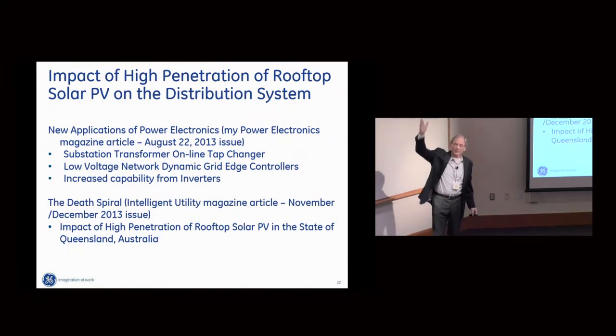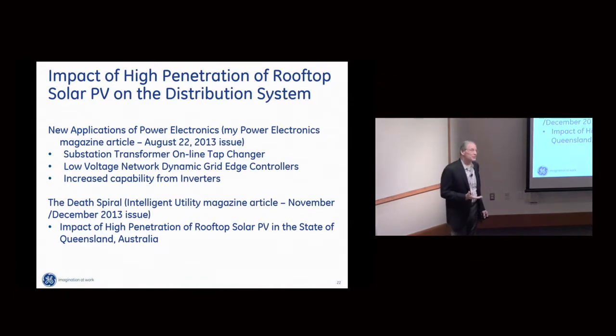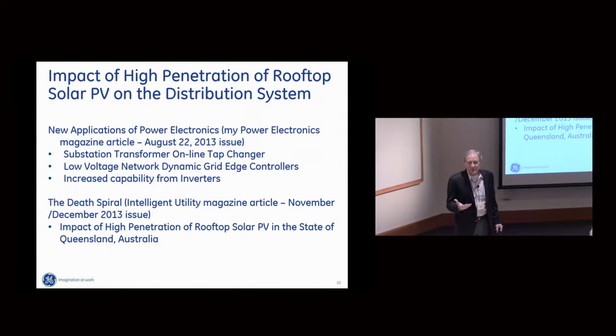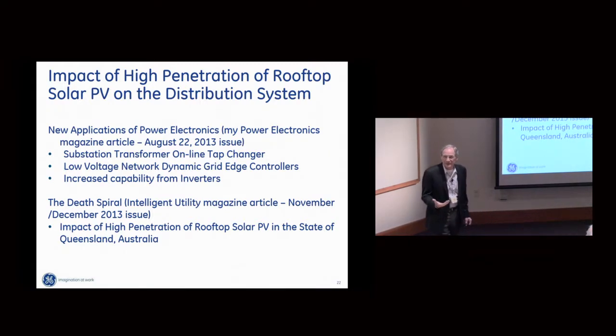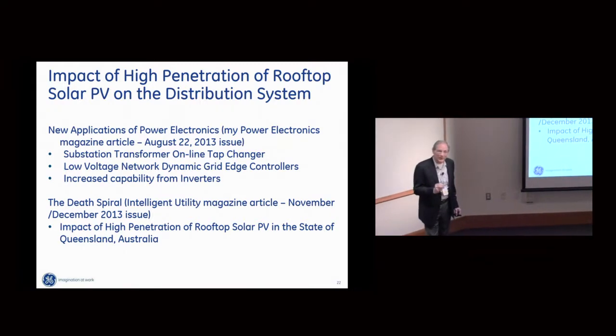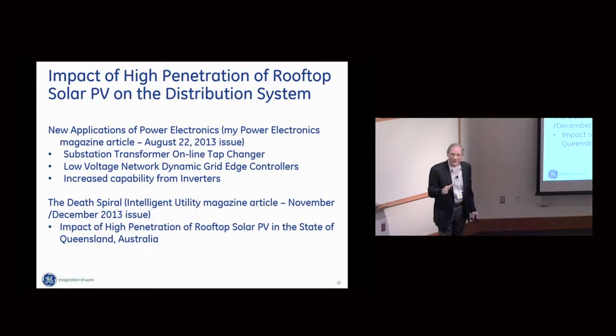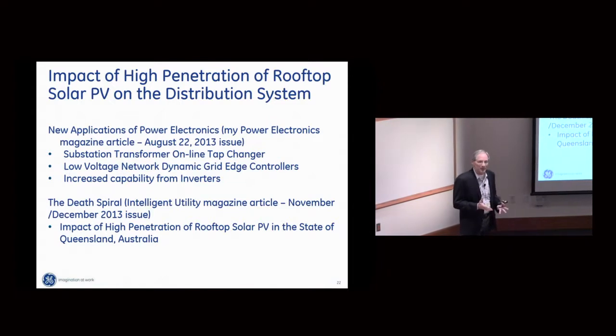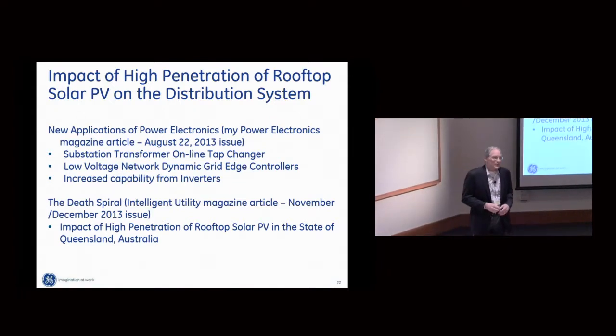It spiked and then oscillated as clouds and things moved. So what happened to the tap changer in the substation? The tap changer is mechanical — 16 positions up, 16 positions down, middle position, 33 positions, 0.5% volts between taps, but it's mechanical. Before PV panels were installed on any homes, it was designed with a 35-year life, operating about 5 to 10 times per day.